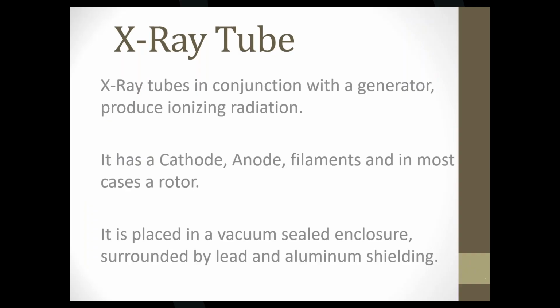So in conjunction with the generator, you have your X-ray tube. It has a cathode, anode, filaments, in most cases a rotor. It's placed in a vacuum sealed enclosure surrounded by lead and aluminum shielding. And like I said, most of your general X-ray systems are fairly straightforward, nothing too complicated, which also makes a hybrid useful. Say you have a large network with a lot of clinics that you have to take care of and they have an X-ray room, this would be a perfect way to point your hybrid tech to get some real-time experience and to work on systems that maybe aren't in as high demand as, say, the hospital would be.